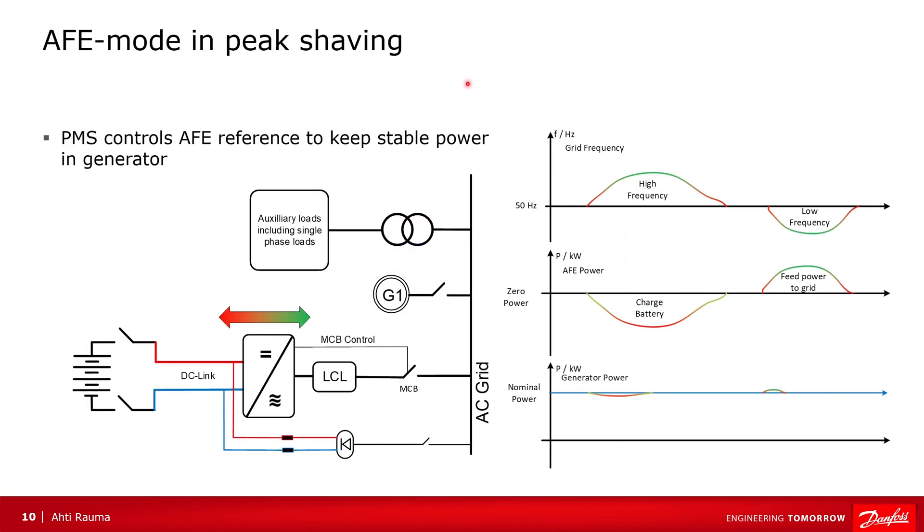One use case for the active front-end is peak shaving. In this case the active front-end is connected to a battery. We have generators and loads on the grid. When the generator is running at its nominal power — basically its most efficient point — and the load on the grid decreases, this causes the frequency to increase. To prevent generator load decrease, we can use this extra power to charge the batteries, keeping constant power for the generators. Similarly, if the power demand increases on the grid, the frequency starts to decrease, and the active front-end can feed power to the grid, keeping constant load for the generator.